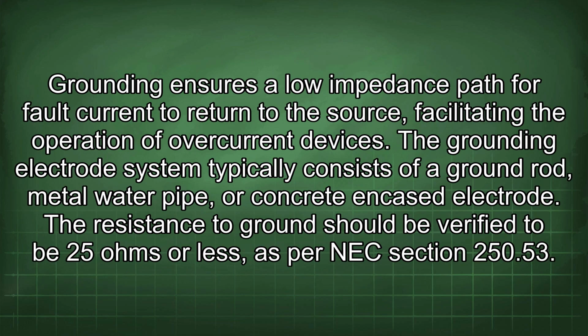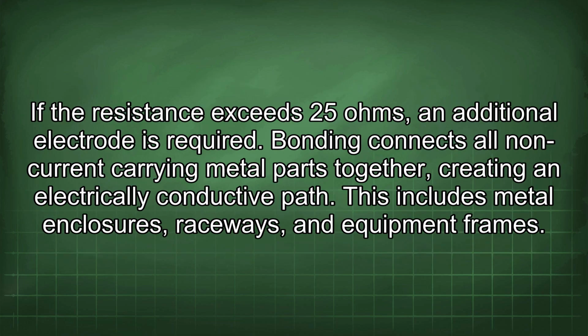Grounding ensures a lower impedance path for fault current to return to the source, facilitating the operation of overcurrent devices. The grounding electrode system typically consists of a ground rod, metal water pipe, or concrete encased electrode. The resistance to ground should be verified to be 25 ohms or less, as per NEC section 250.53. If the resistance exceeds 25 ohms, an additional electrode is required.